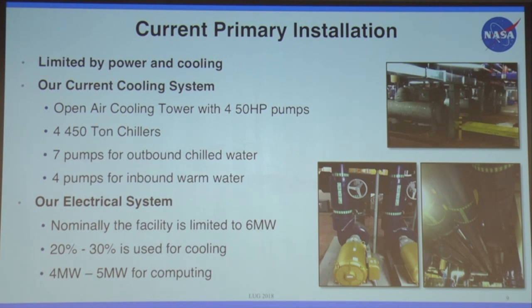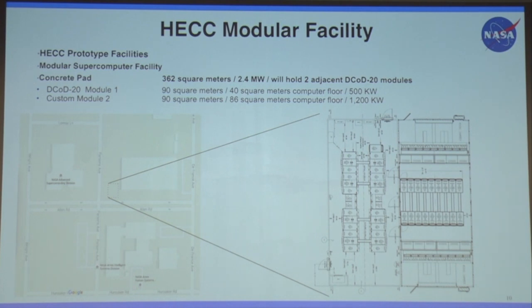So we've built 2 modular test beds. They sit in the parking lot across from our main building, and these are modular, space purpose-built computer buildings that drive PUE down to about 1.04. There are 2 different types of those kinds of facilities: one is all air, and one is primarily water and self-contained. The advantage is that we get about double the density, and we can drive configurations like GPU or Xeon Phi in that facility and cool it with ambient air, so no compressors involved.